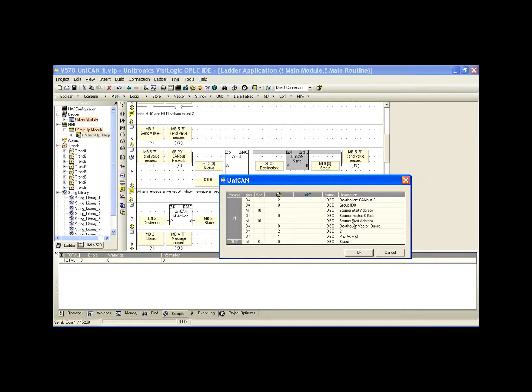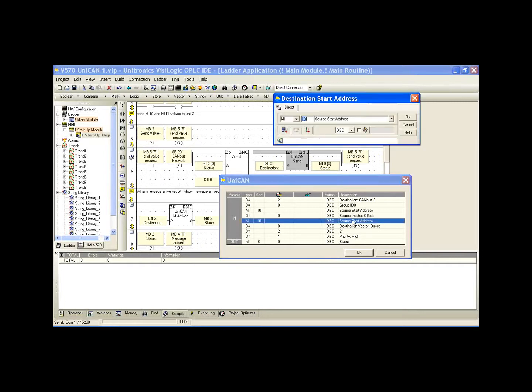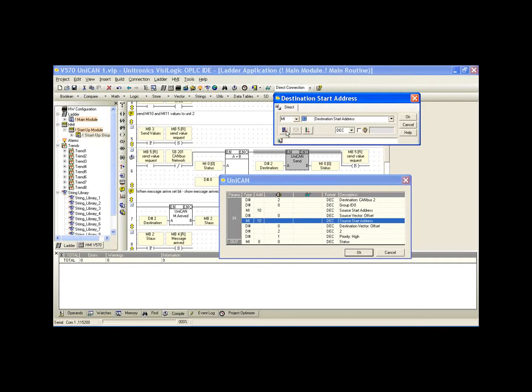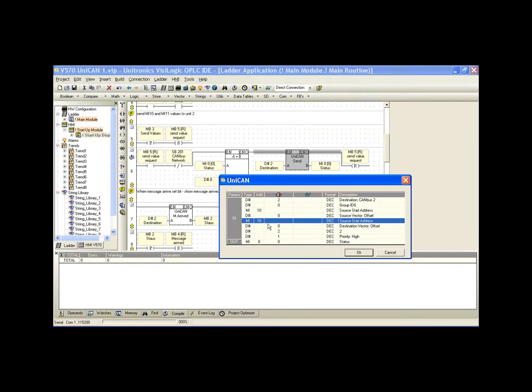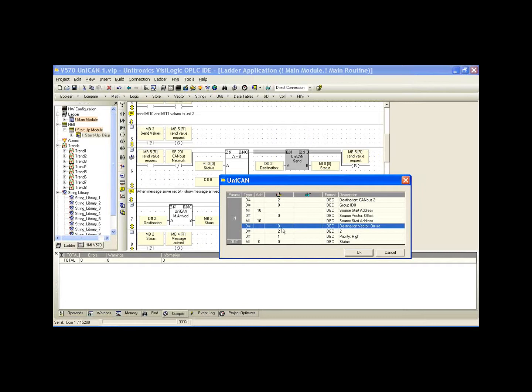What we see is the description source start address. Actually, this is the destination start address. Because we've already given a description as MI10 and we're sending to our other controller as MI10, we can't have two different descriptions for MI10. But if I click the next get unused, you'll notice the description is destination start address. This is the address that we're sending to in our other controller, our controller 2. I'm not going to change it from 10. We see below, again, the destination vector offset. So if we set it as 2, we would send MI10 to MI12 in our controller 2.